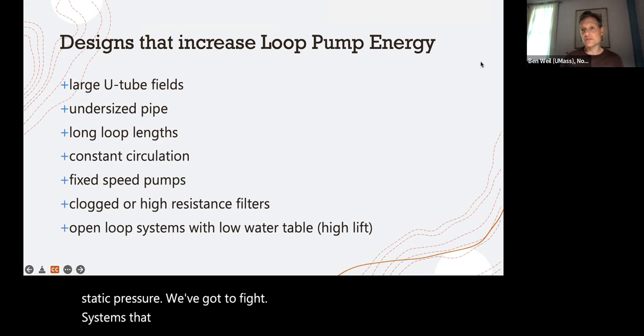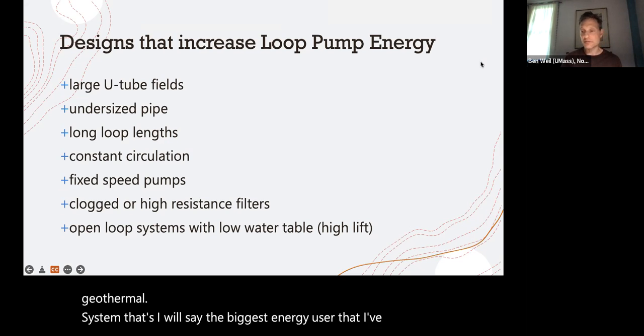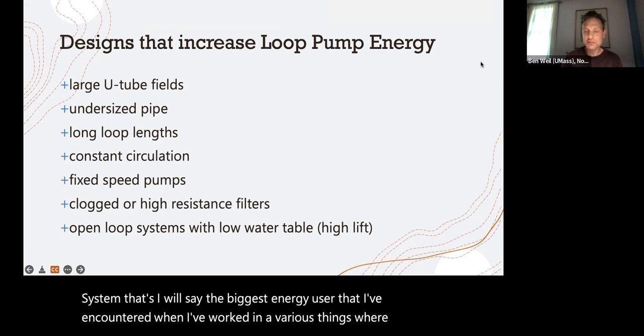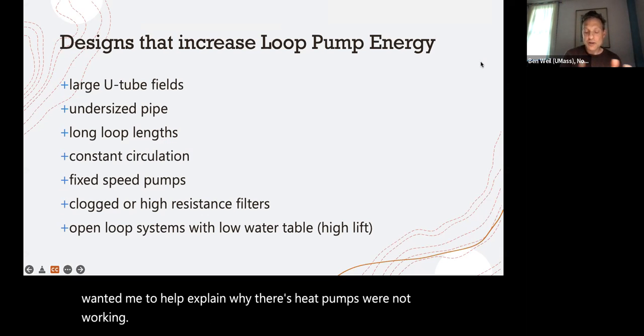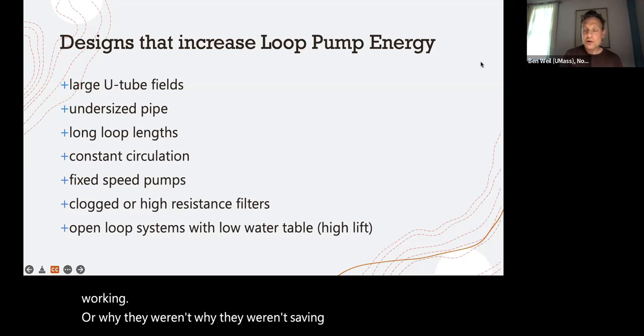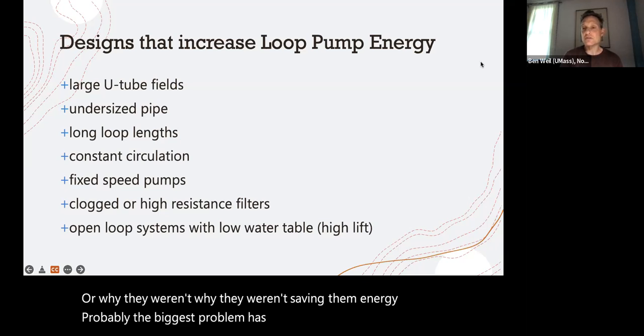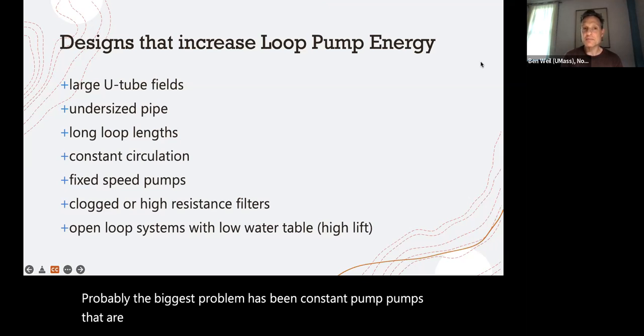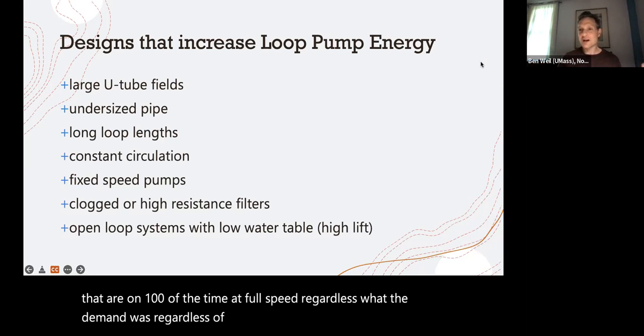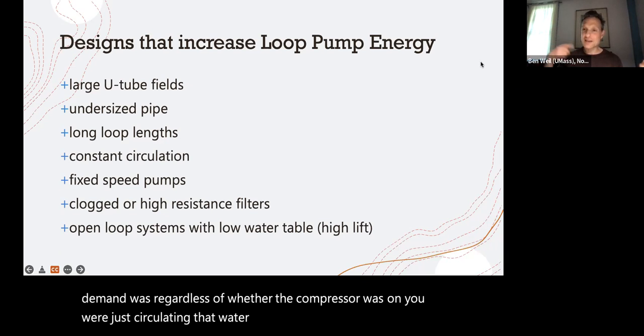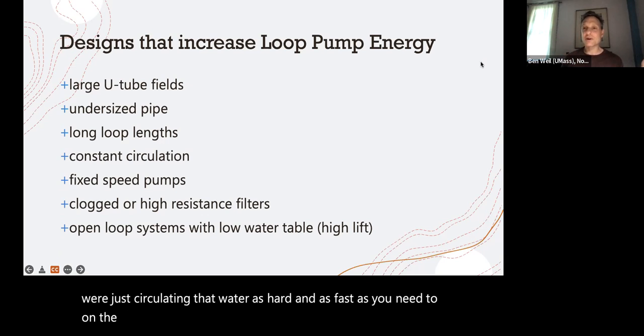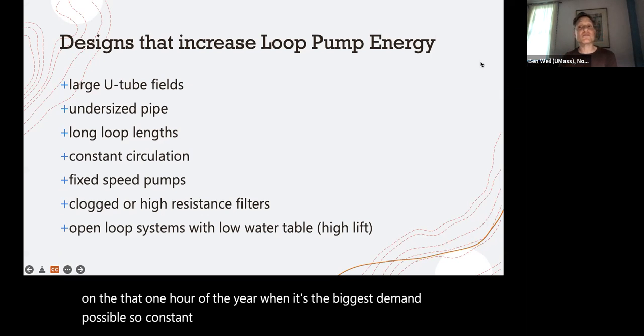Systems that are designed for constant circulation in the geothermal system, that's, I will say, the biggest energy user that I've encountered when I've worked in various things where people wanted me to help explain why their heat pumps were not working, or why they weren't saving them energy. Probably the biggest problem has been constant pumps that are on 100% of the time at full speed, regardless what the demand was, regardless of whether the compressor was on. You were just circulating that water as hard and as fast as you need to on that 1 hour of the year when it's the biggest demand possible. So constant circulation and fixed speeds.